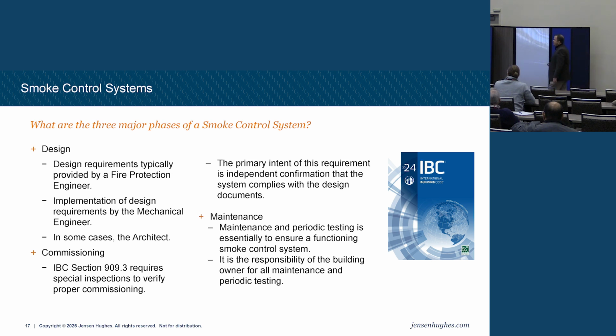But the International Building Code 909.3 requires special inspections to verify proper commissioning. If you call my company or a consulting firm and say, I need a special inspection for a smoke control system, we already know what that means. That in itself is a definition. The primary intent of the requirement is to independently confirm that everything works. That complicated sequence of operations I described gets really complicated on these systems, so we want to test every single piece. And then the maintenance.